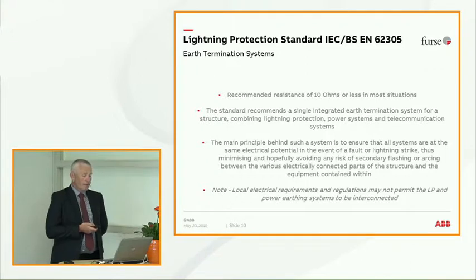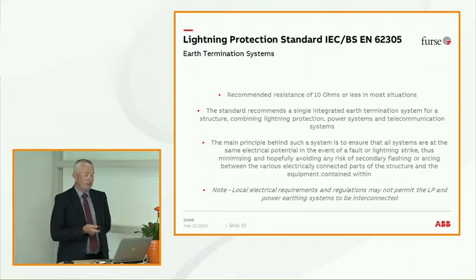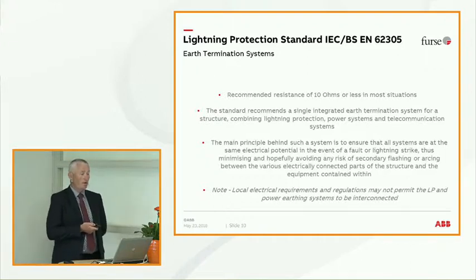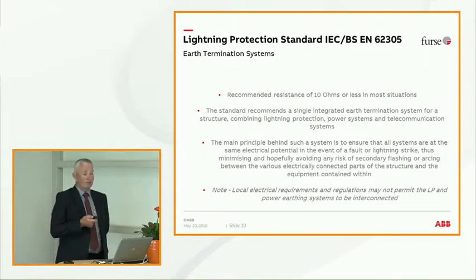On an earth termination system for lightning protection, the earthing requirement is 10 ohms or less per earth. The standard recommends a single integrated earth termination system for a structure, combining the lightning protection, power systems and telecommunication systems. The main principle behind such a system is to ensure that the system is at the same electrical potential, so you've got that ease of current going to earth.